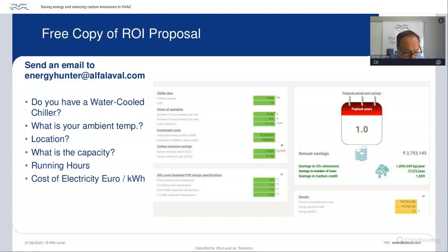So to sum up, energy savings, absolutely crucial with every step that we take. And energy savings is adopted into our heat exchanger design, especially distributing the flow through the channels, avoiding and minimizing fouling, keeping pump costs to a minimum, and making sure that the heat exchanger is efficient with the pumping power that we are using. And secondly, the application of protecting the condenser. One heat exchanger can also in winter help to turn that chiller off. And the savings, of course, how many days a year that you can turn it off.